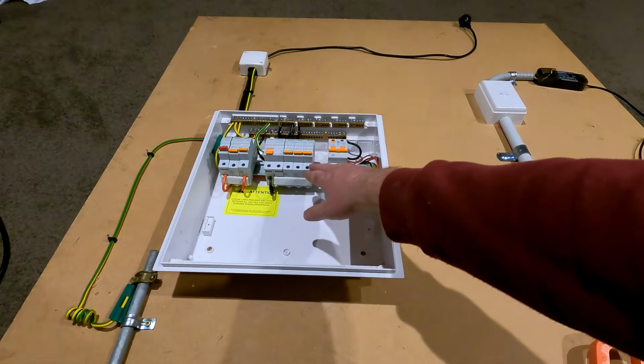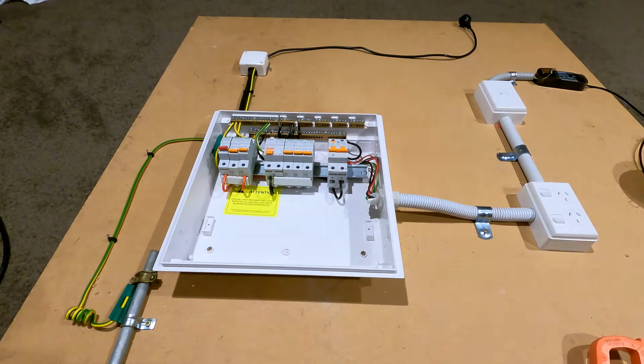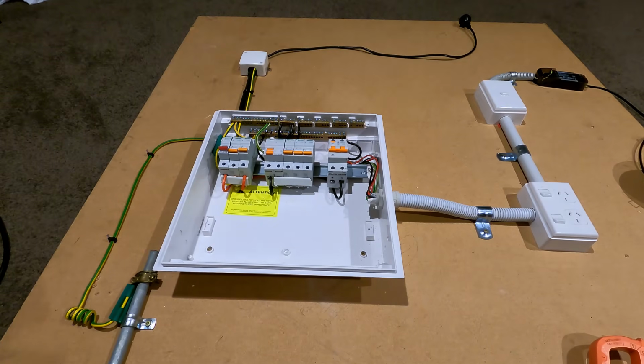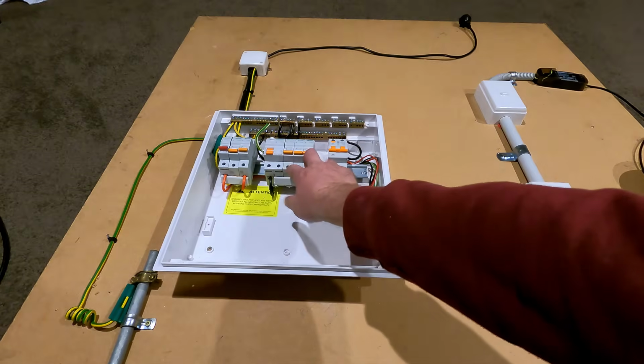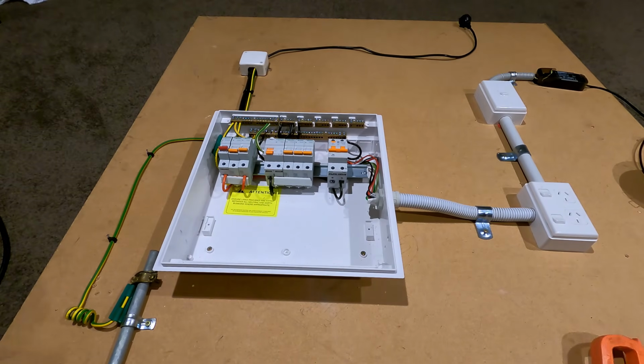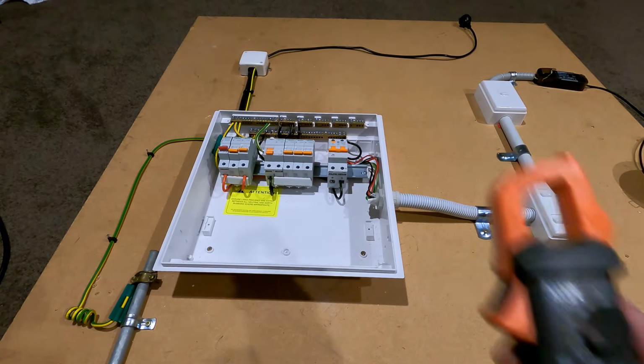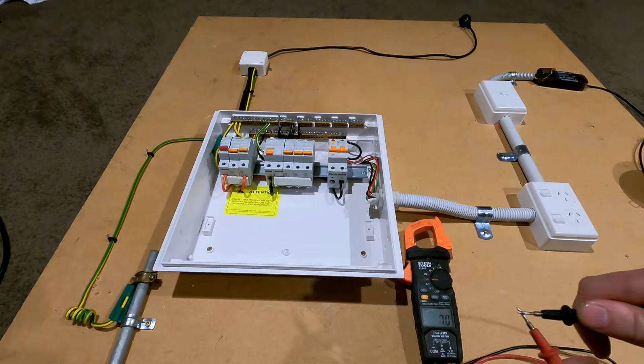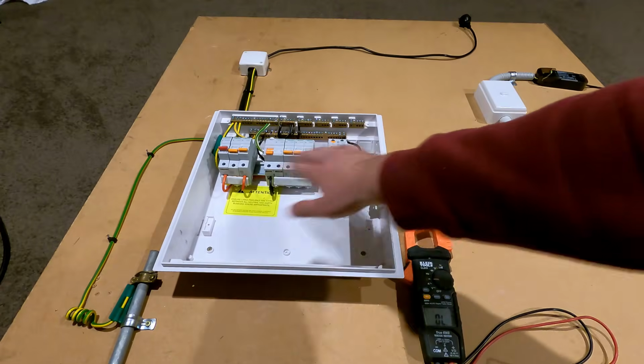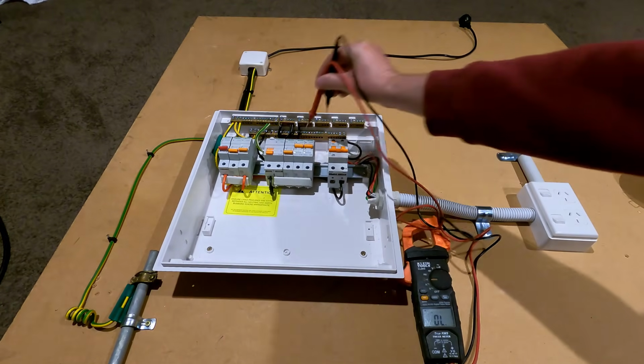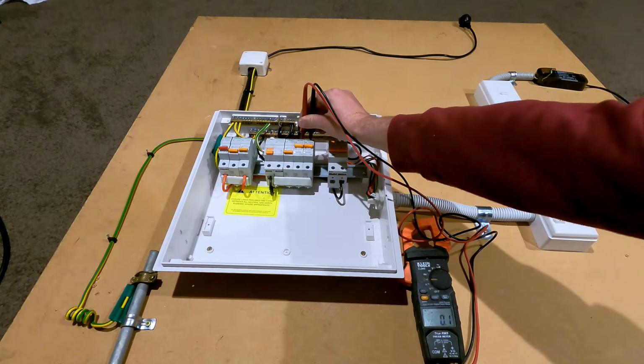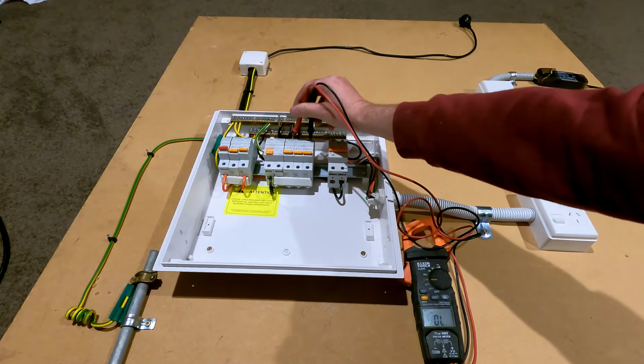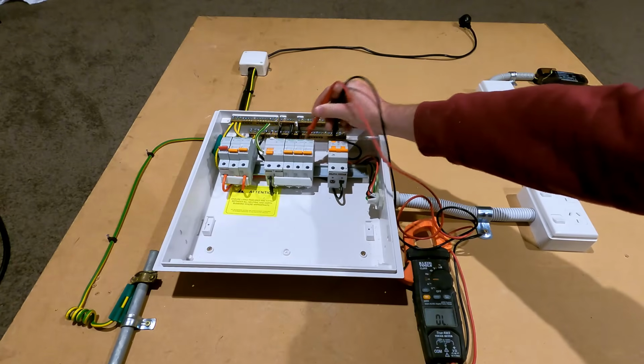So we don't want any cable coming off any particular breaker interconnected with a different breaker or different RCD, although that's going to throw up an RCD fault straight away if it was on a different RCD circuit. But in particular, we want to be testing and ensure that each circuit is separate. Now it's pretty easy on this one, there's only the 2 circuits. So I'll test between them just to show you guys. All you want to do is put your meter on continuity. It's going to beep. So make sure the breakers are turned off, or there's going to be continuity. And as soon as they're off, there's no continuity. Now you could go around, test the whole lot, make sure nothing interconnects.